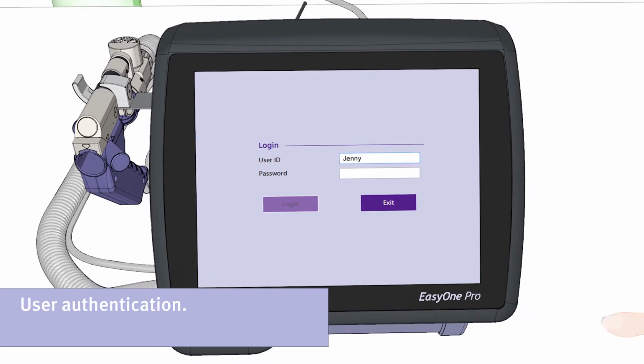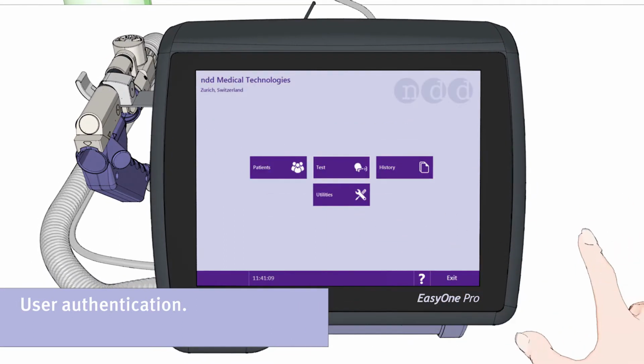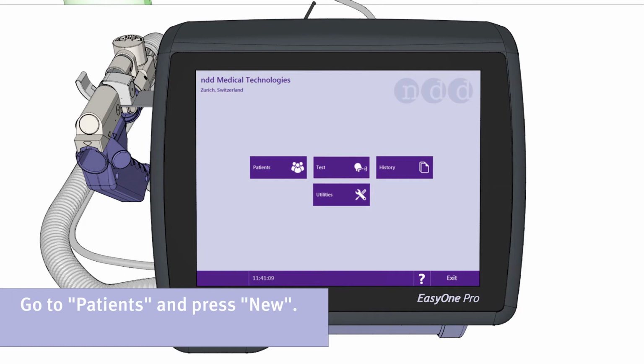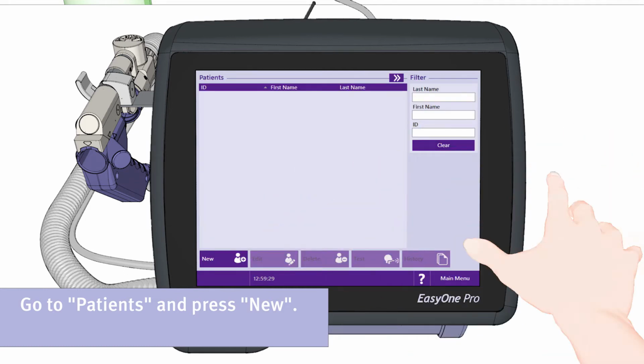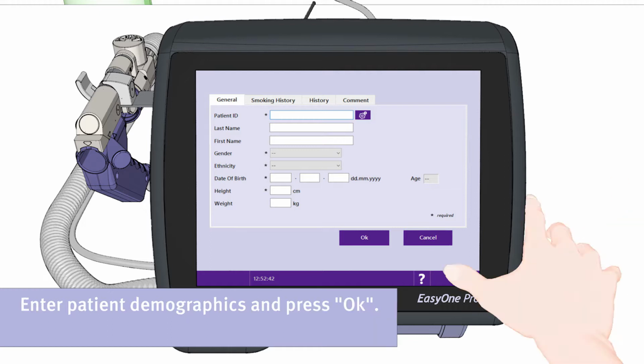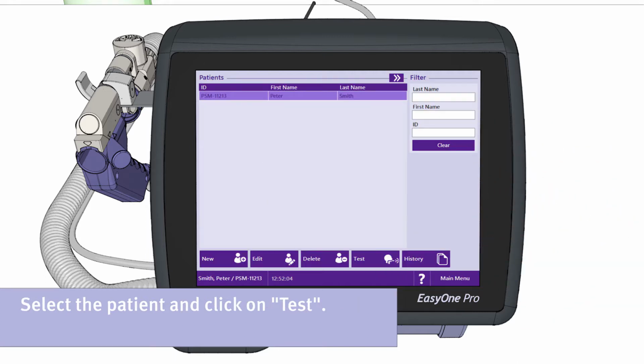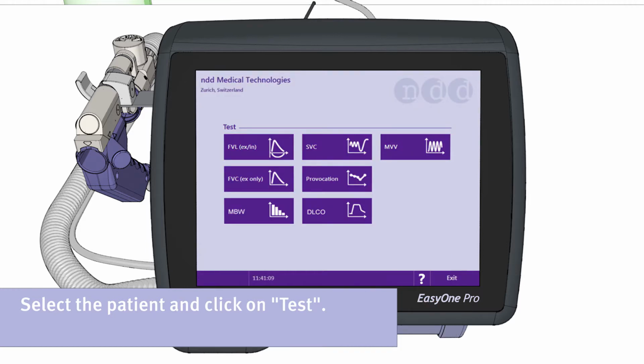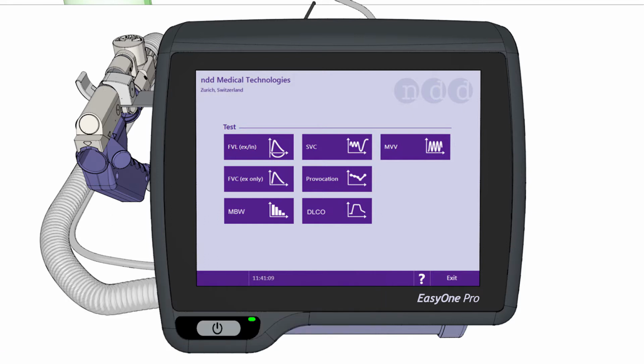Before you can enter the patient data, you need to authenticate yourself as a user. Please click the button Patients, then press New to enter a new patient. Enter the patient demographics and then press OK to save the data. Now select the patient and then click the button Test to select the respective examination you want to perform on the patient. To start the examination, perform a spirometry test first, for example, an FVC or FVL test. In this case, we show an FVL test.